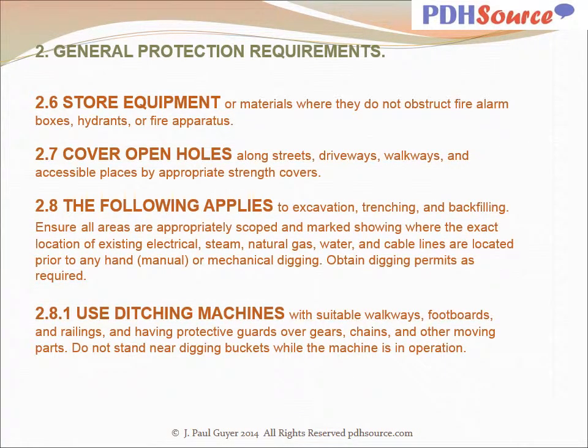Store equipment or materials where they do not obstruct fire alarm boxes, hydrants, or fire apparatus. Cover open holes along streets, driveways, walkways, and accessible places with appropriate strength covers. The following applies to excavation, trenching, and backfilling. Ensure all areas are appropriately scoped and marked, showing the exact location of existing electrical, steam, natural gas, water, and cable lines prior to any hand, manual, or mechanical digging.